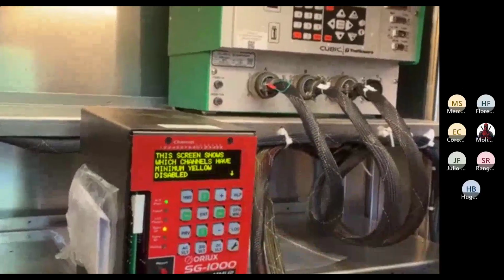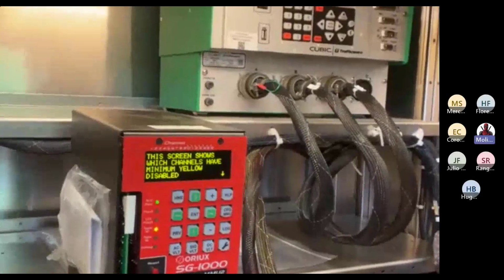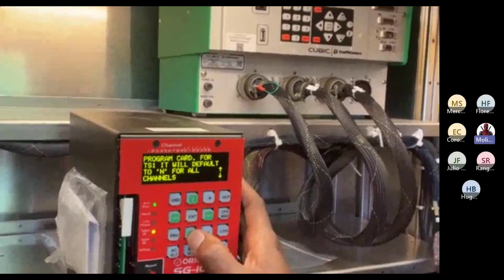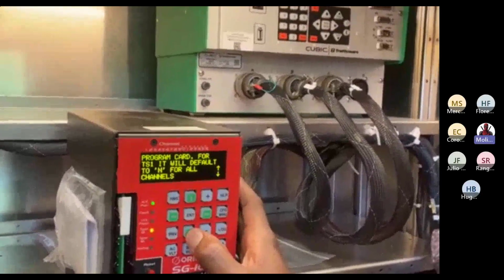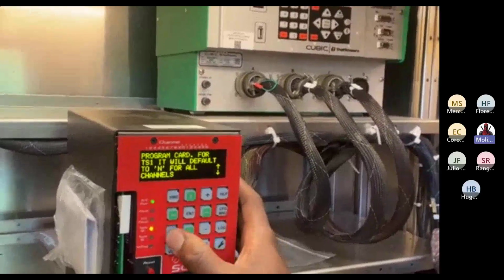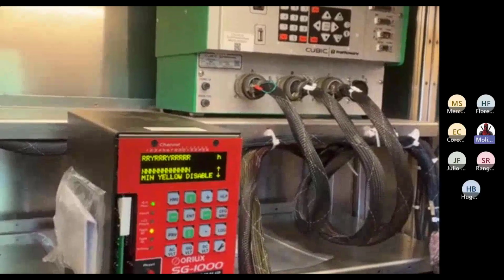You have to go into a different screen for that one. No, multi-indication. Like I said, they do slightly different things depending on what you're doing. If you're not using it, or if it's flashing, it depends on which one you need to do, right? So if it's flashing, then you just need to do the minimum yellow disable, to ignore the timing of it, but it's still there. It works. It does what it's supposed to do, right? But if you're not using it at all, you just turn it off. You have it not monitor it with the multi-indication.